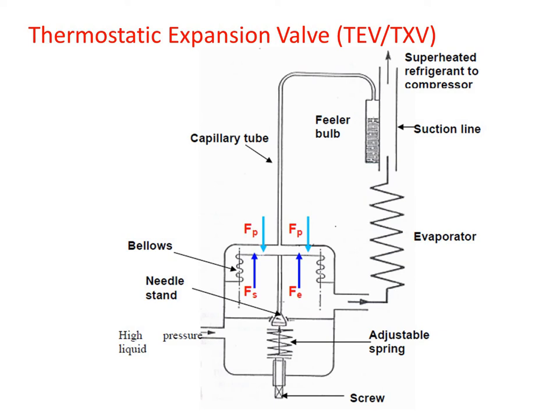The various parts of the thermostatic expansion valve are: capillary tube, feeler bulb, suction line, superheated refrigerant outlet to the compressor, adjustable spring, screw, bellows, and needle seat. High pressure liquid enters from one side and refrigerant is fed to the evaporator and then to the suction line. Any change in degree of superheat of suction gas alters the valve position. If the degree of superheat is less than 5°C, the sum of evaporator and spring pressure exceeds the pressure exerted by the bulb, tending to close the valve and throttle flow to the evaporator until the desired degree of superheat is obtained.